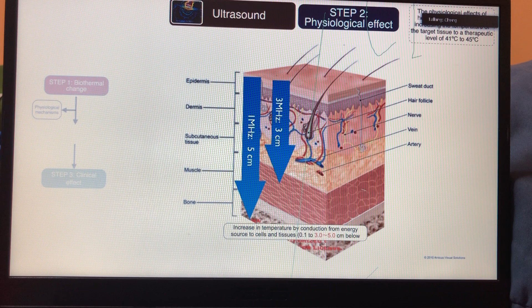Okay. So at 3 cm, you'll see that you're already reaching past that Goldilocks zone for 1 megahertz, but we'll come back to that again. Very short. And 4 cm, again, not that great. At 5 cm, 1 megahertz is just touching anyway. It's not really that bad. So for 1 megahertz, if you really look at the error bars and so on, you can get physiological effects maybe up to about 4 to 5 cm. But at 3 megahertz, you're looking at even less than 3 cm, even 2 cm or less. So 3 megahertz is really limited in the way that you can deliver energy to the target tissue.